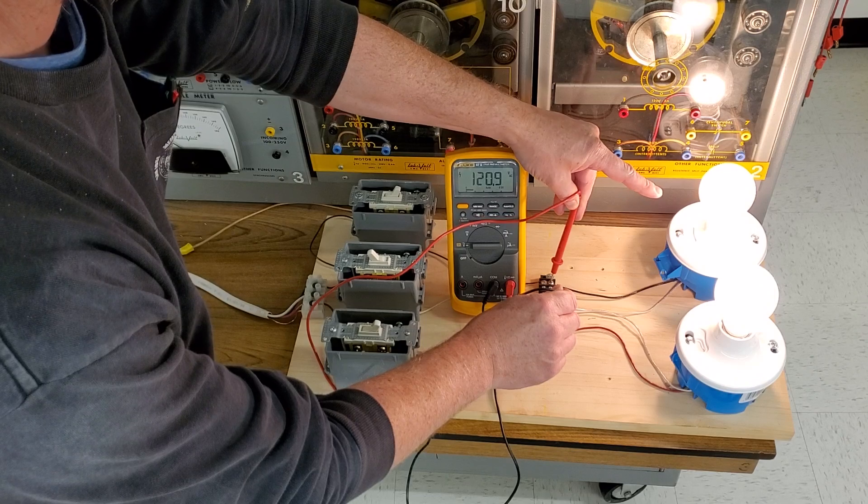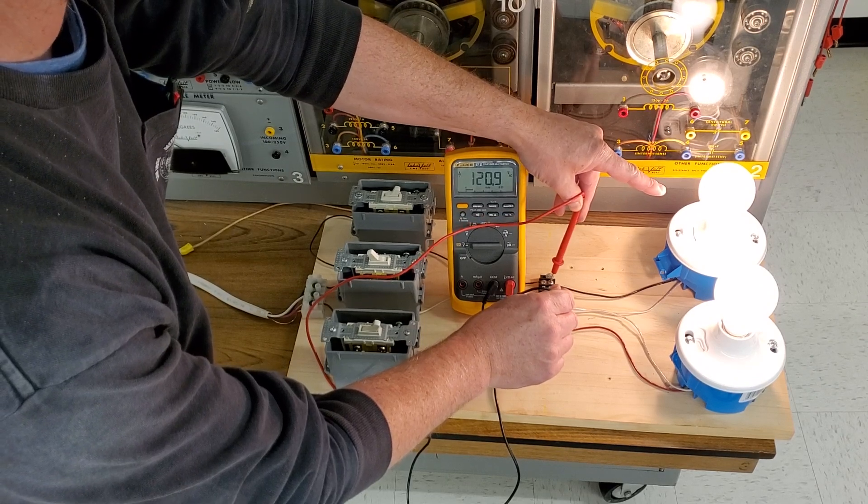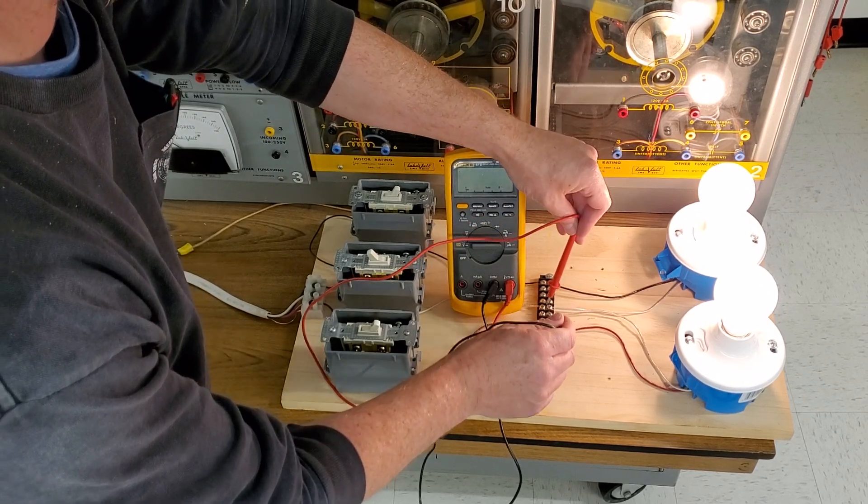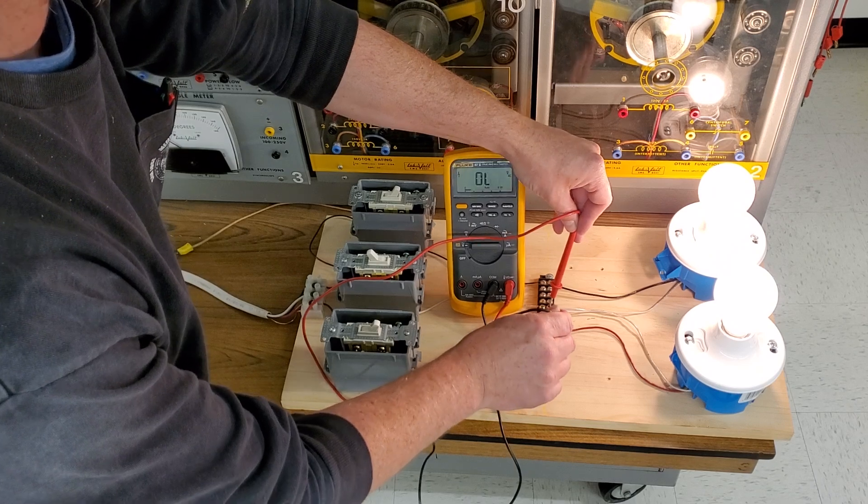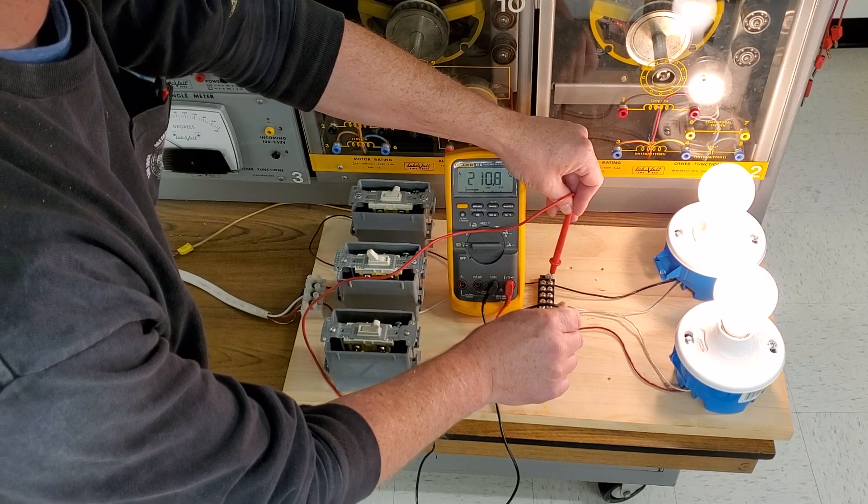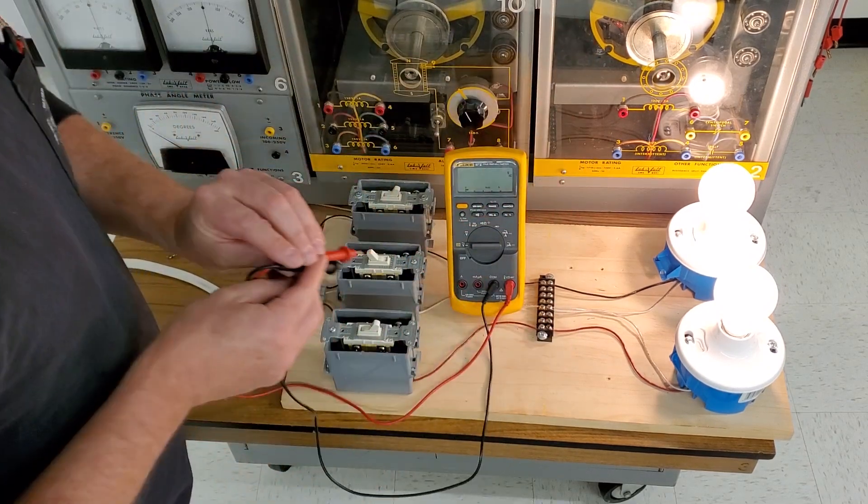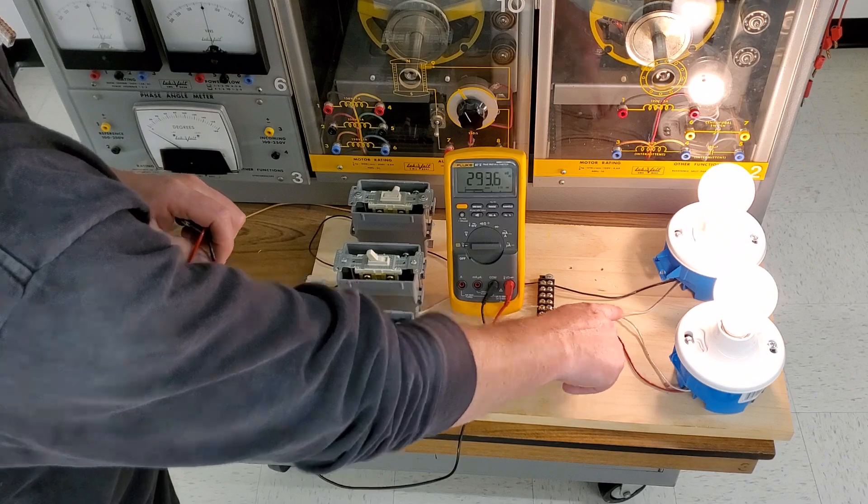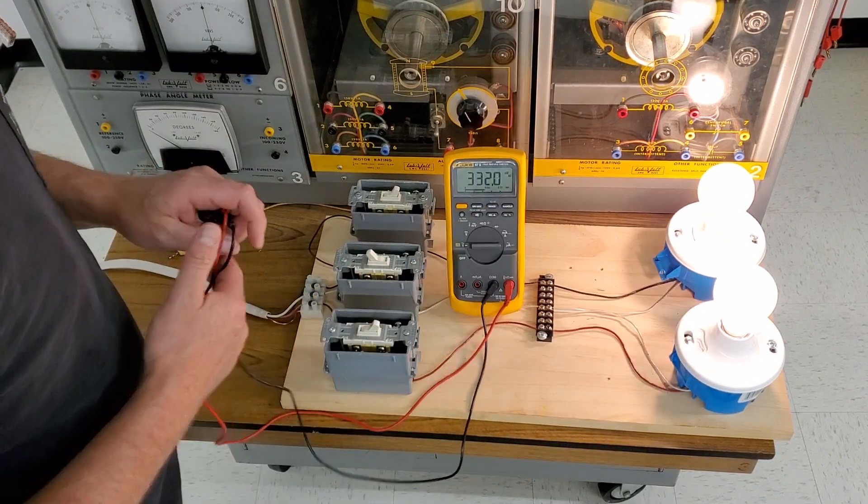And with this bulb here we're only reading 90 volts, and that totals up to 210. Once we lose our neutral and we're in series through our bulbs, if these were of more different resistances, we could cause one of these sensitive electronic devices to blow up.